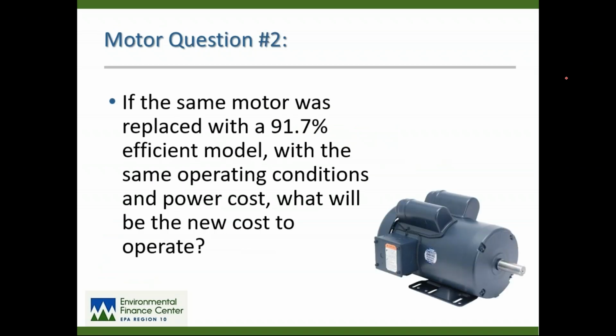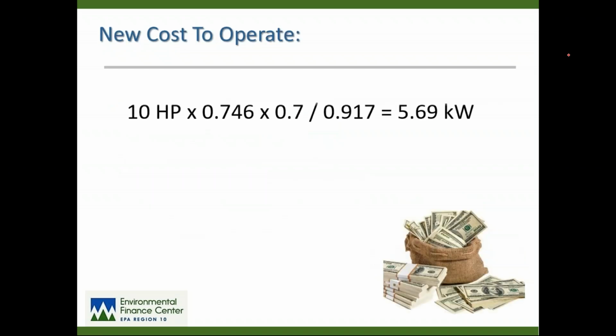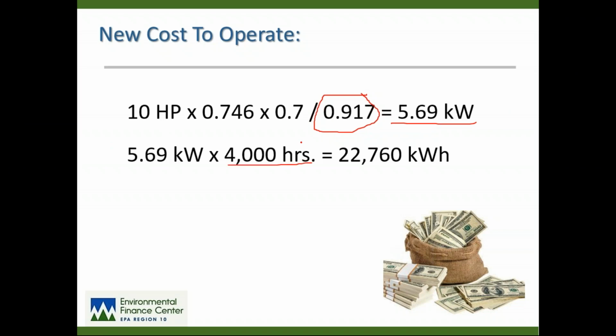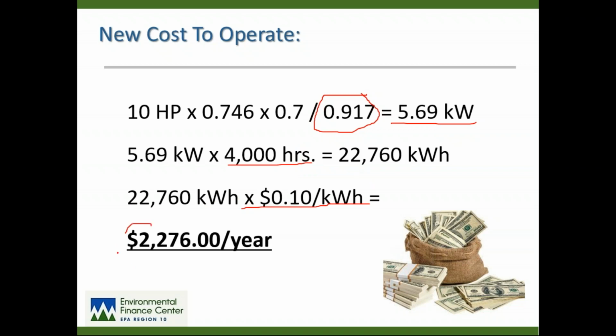Now let's throw a little variable in here. What if we replaced this motor with one that was 91.7% efficient, which is more typical of what you'd see nowadays? Same operating conditions, same power cost. What would be the new cost to operate? So we just run those numbers again, but instead we use 0.917, which is the decimal equivalent for 91.7% efficient. We find now that that motor is only drawing a little bit less than 5.7 kilowatts. We run it out to the hours, we run it out to the years, and then we multiply that times our cost of power. Our new power cost to run that motor is a little bit less than $2,300 a year. So we have immediately seen some savings from jumping up to 91.7% efficient.